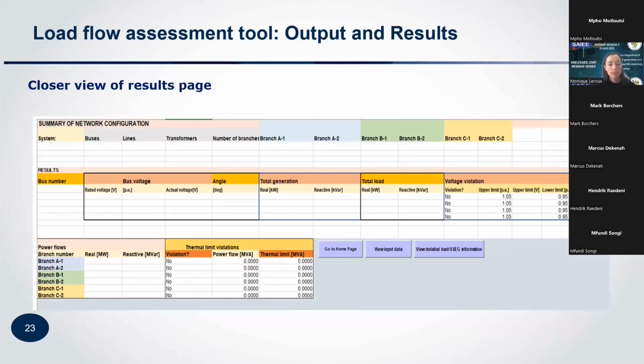And then this is just your output, and your results will be given from that tool into an Excel spreadsheet with a format that looks like this, where you will be able to just see a summary of your network configuration, just to give the user a summary of what their lines and buses, the generation where that's connected. And then it will give an output on your voltage of each bus, your total generation, your total load, and then it will give some output as to whether there are thermal violations, where those thermal violations are, and basically the exceedance. And then also it will give you the same output for your voltage.